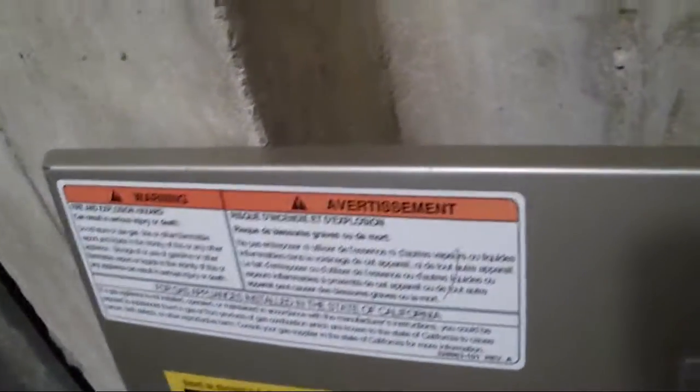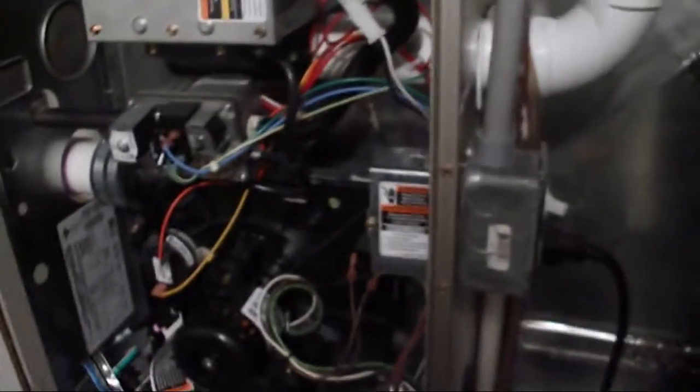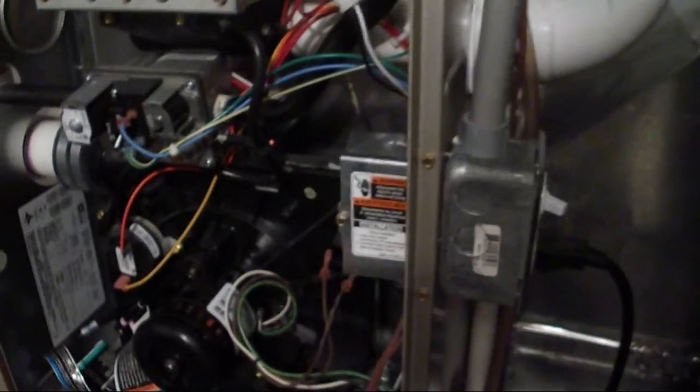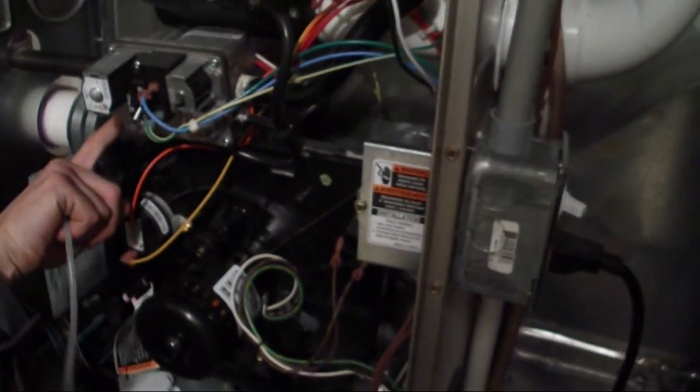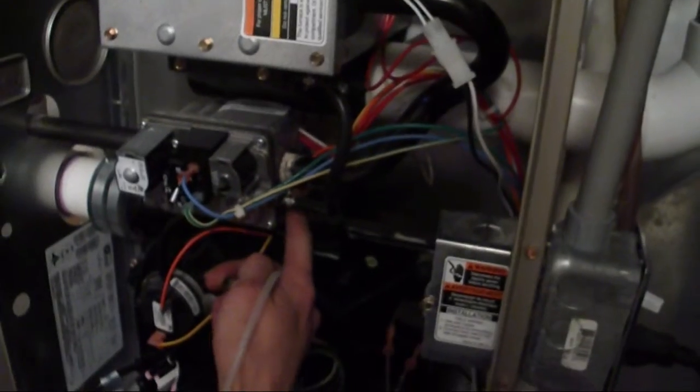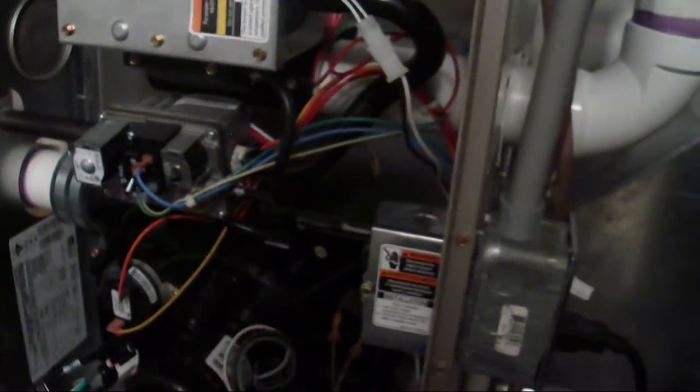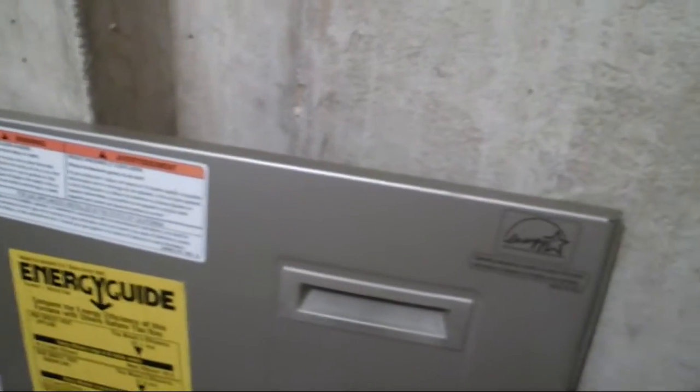So if we were going to take your gas pressure we would use the same thing. And we would just look at it like for this one. This would be your incoming gas pressure. And we would hook that in. And then hook it to your manometer. And then your outgoing would be right here. And that would tell you your outgoing gas pressure. That's only if there's a service call problem. Like if this was real black inside or charred, but everything is running fine.